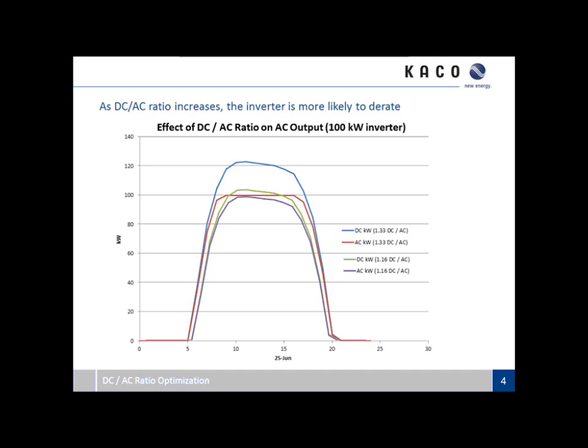This shows a more modestly sized array of 116 kilowatts to a 100 kilowatt inverter, about a 1.16 ratio. You can see the DC is peaking at around 105 kilowatts. The only loss is wiring and inverter efficiency — the inverter is not clipping at all, so you're utilizing all of the array's potential and it's getting turned into AC power. But if you look at the difference between the AC curve at 1.33 and the AC curve at 1.16, that area between the two curves is lost energy production. That's the rationale some people have for increasing the DC to AC ratio — to maximize energy harvest.